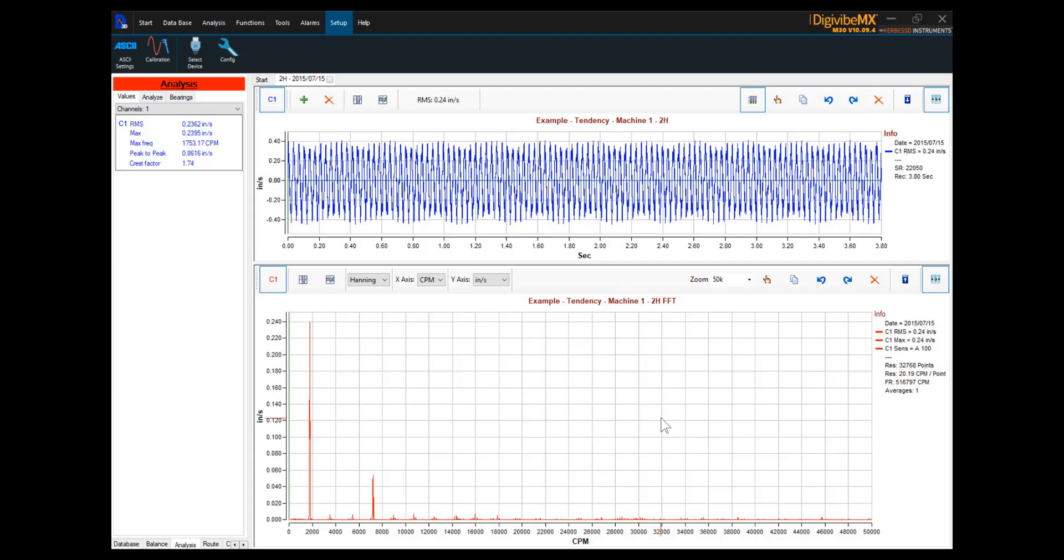Lines of resolution determine the frequency range represented by each individual peak in a Fast Fourier Transformation, or FFT, spectrum. The individual peaks at a lower-resolution FFT will encompass more frequencies than peaks in a higher-resolution FFT. At low-resolution, it is possible for two components very close in frequency to become consumed by a single FFT peak.